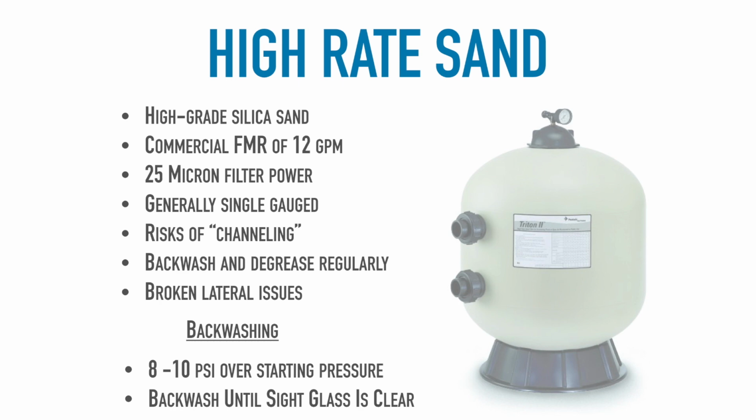Now, the reason why I recommend that you replace all of them at once is because we don't know which one of those is broken necessarily, because some of them can have really hairline cracks that only reveal themselves once they're under pressure. So as a result, I recommend that you just replace all of those laterals all at once.